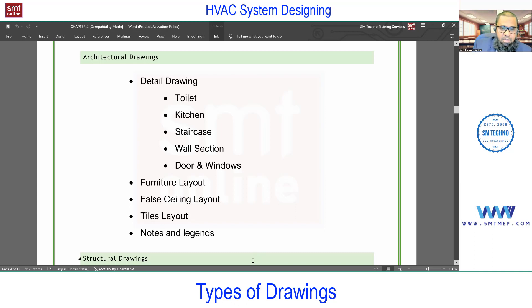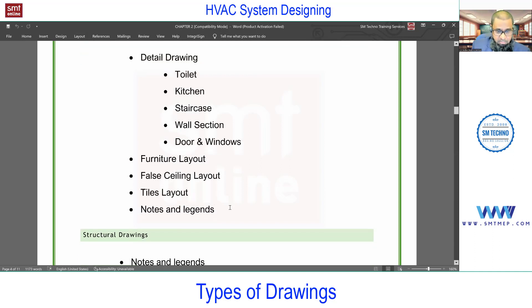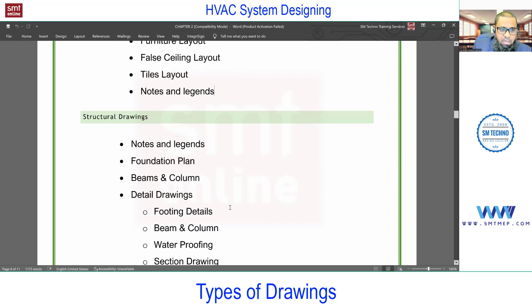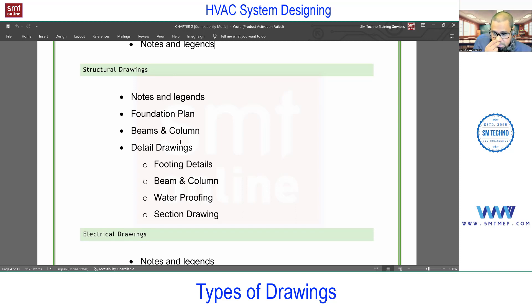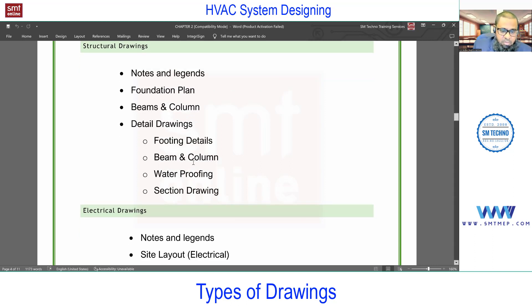For architectural drawings you'll also find floor plans, sections, and elevations which are required, and we'll learn how to read these in detail in building survey. For structural drawings, you'll find notes and legends, foundation plan, beams and columns. Beams and columns are required for coordination purposes — we cannot run ducts through beams and columns. We can run ducts through slabs, but that must be coordinated at the design stage with the structural engineer, as large openings in slabs affect the structural load of the building.